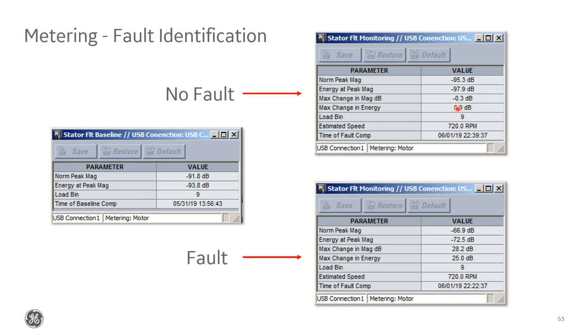If a fault were to occur, you should see something like this bottom screen, where you can see the magnitudes have increased quite a bit. And this is reflected in the max change values that show a change of about 28 and 25 decibels. Ideally, the pickup settings would be set somewhere around a 20 decibel change. So in this case, if this change value is sustained for some time, then the ESA stator element would have picked up an alarm that something's wrong.